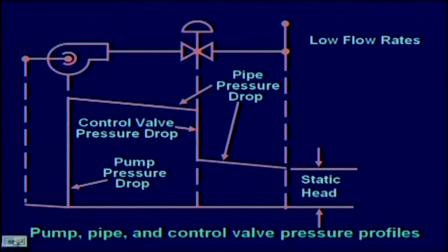Now, one must realize that if you actually put the valve into an application and connect it up with other components, pumps, systems, pipes, etcetera, then the inherent characteristic will not be realized. So, the stem lift versus flow characteristic of the valve, which is provided by the manufacturer, which is the inherent characteristic, will not be realized because delta P will not remain constant. So, how does that happen?